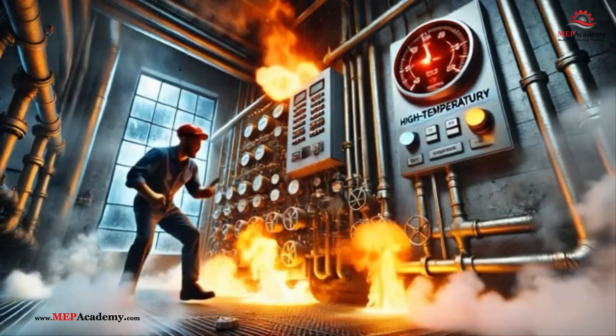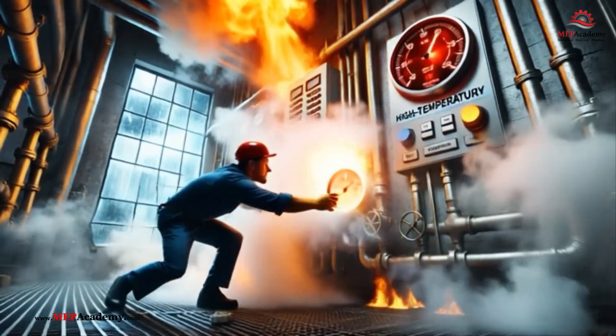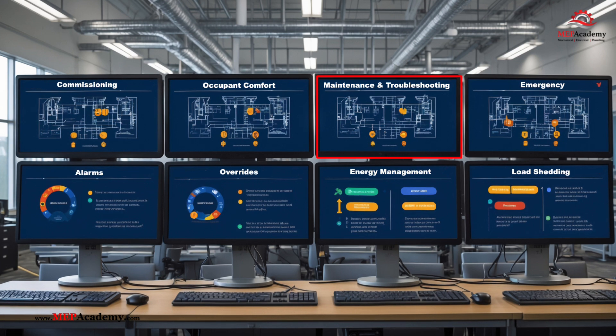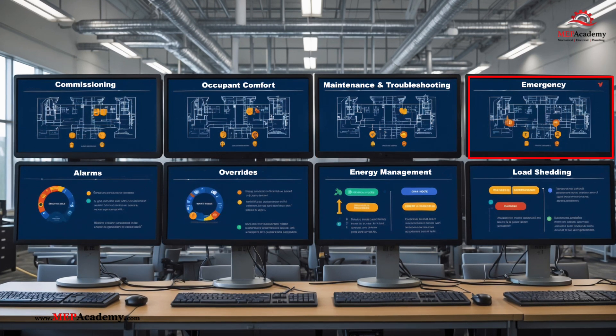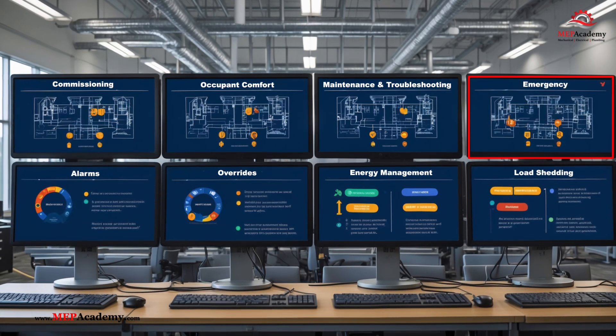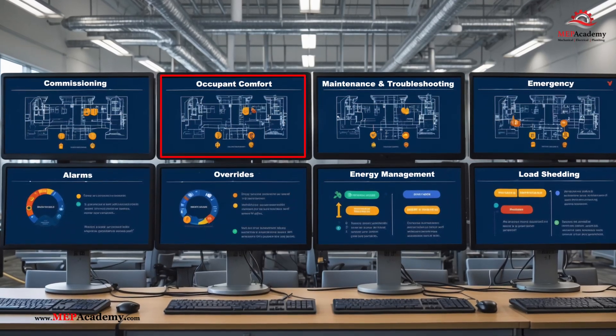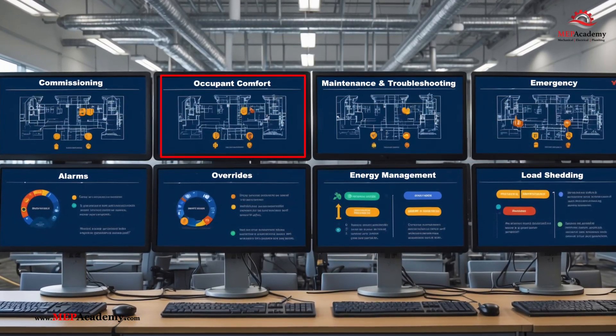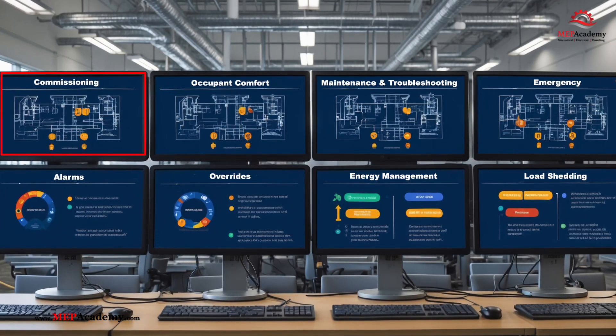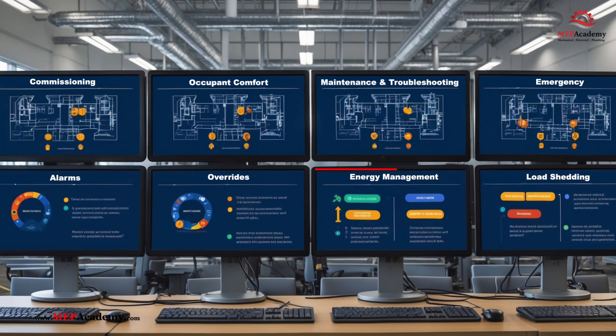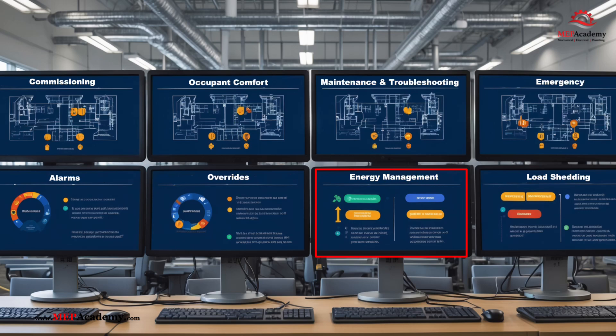Purpose of overrides: Overrides serve several key functions in building automation. Maintenance and troubleshooting allows testing and diagnosis of individual equipment without automation interference. Emergency situations ensure critical systems such as smoke evacuation fans or fire suppression operate regardless of the control logic. Occupant comfort adjustments temporarily modify set points to accommodate specific user needs. Commissioning and calibration verifies system responses during initial setup or post-maintenance. Energy management and load shedding overrides can help reduce energy costs by temporarily disabling non-essential loads.